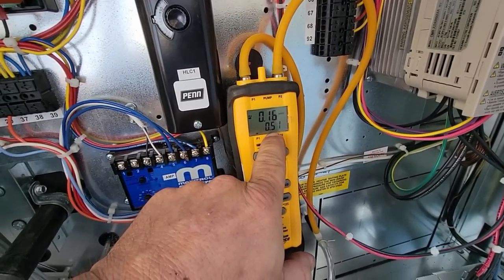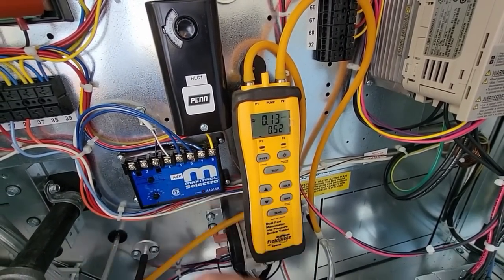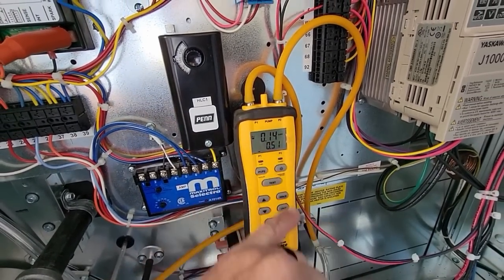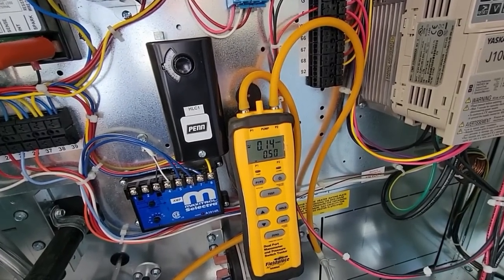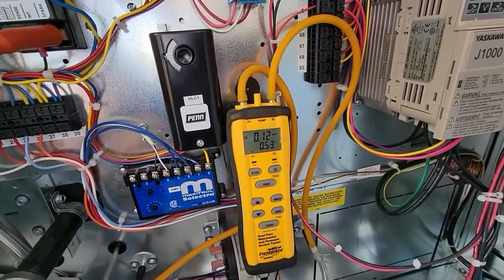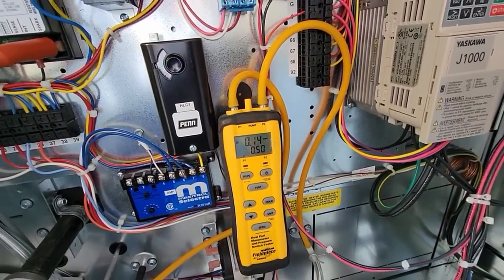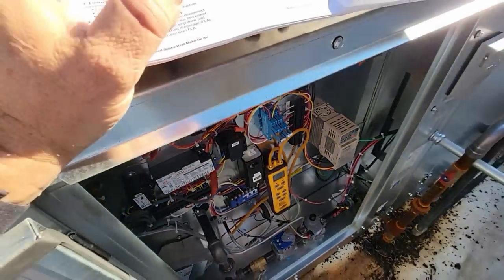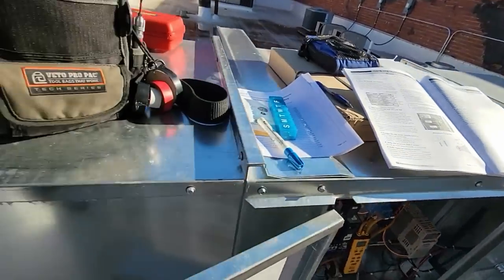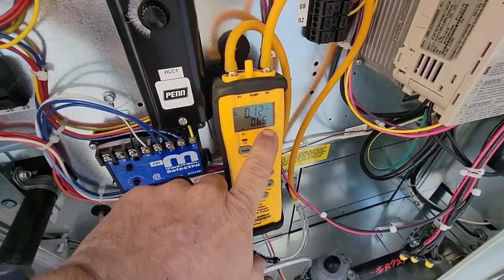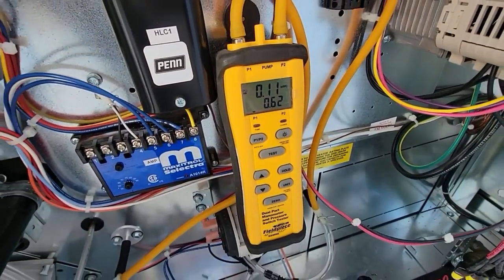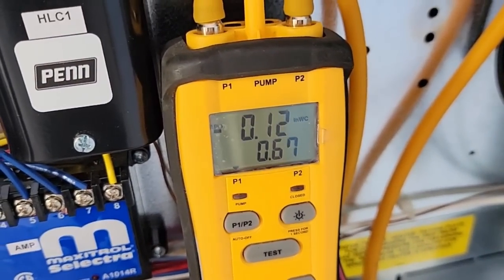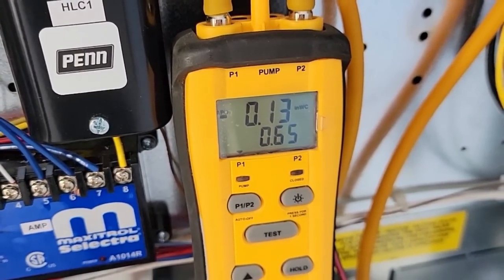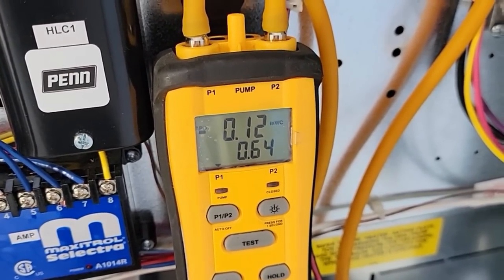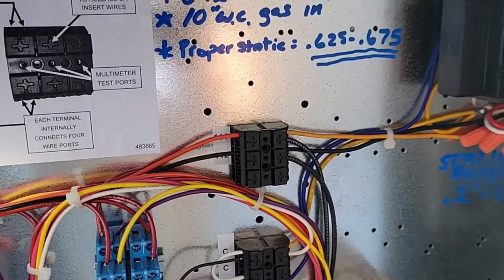So we're only at 0.5. That's still not where they want it at, that 0.625. So like I said, you probably have to close it completely down. That just seems like always the case. It must be when they have completely screwed up ductwork that it doesn't work out right. So we'll do another adjustment here. We made one more adjustment. Now we're at 0.65, between 0.62 and 0.67. So that looks just about right where they told us to put it, don't it?